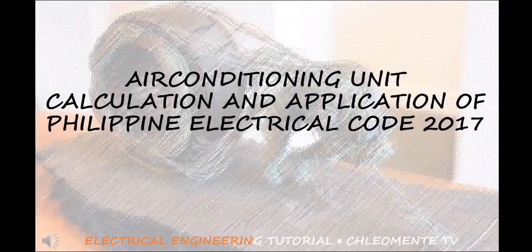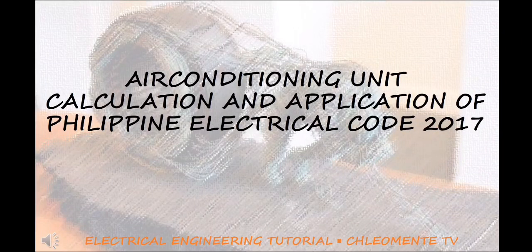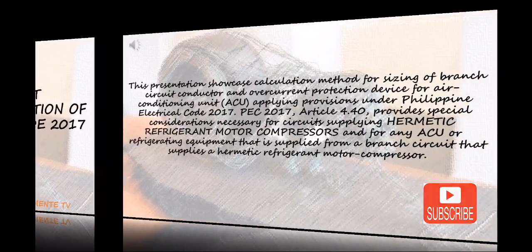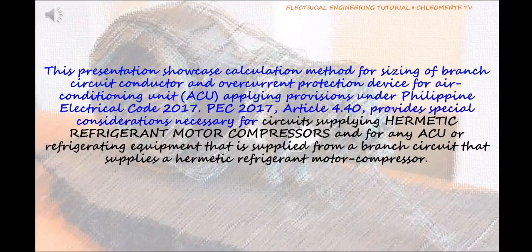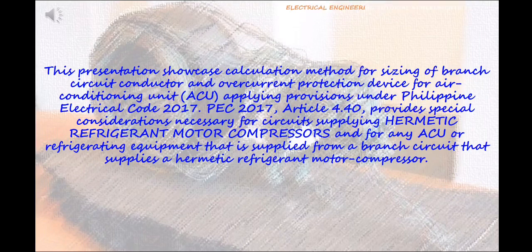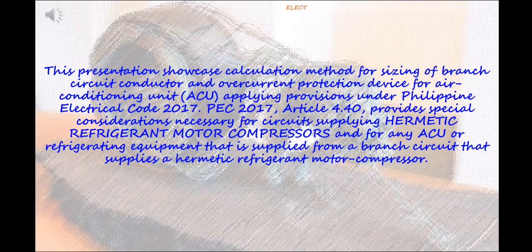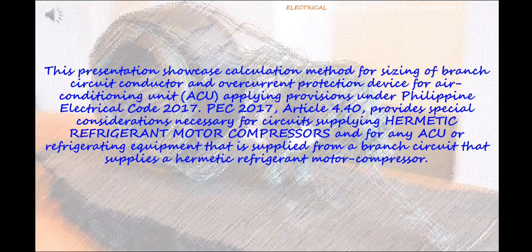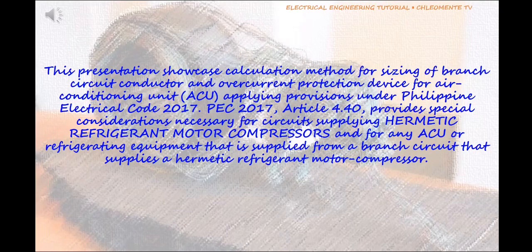Air Conditioning Unit Calculation and Application of Philippine Electrical Code 2017. This presentation showcases calculation method for sizing of branch circuit conductor and overcurrent protection device for air conditioning unit (ACU) applying provisions under Philippine Electrical Code 2017, PEC 2017, Article 4.40, which provides special considerations necessary for circuits supplying hermetic refrigerant motor compressors and for any ACU or refrigerating equipment that is supplied from a branch circuit that supplies a hermetic refrigerant motor compressor.